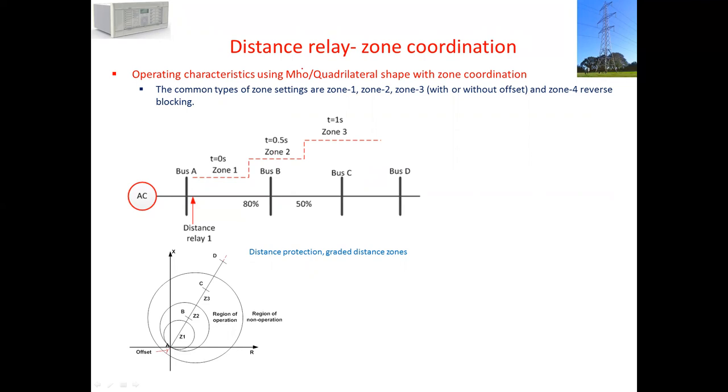If we look at the Mho shapes, the line between A to B is this one. We cover 80%, so around 20% is a gap. Everything within this circle, the relay must operate in zone 1 time, instantaneously. Zone 2 is at 50% of the next line between B to C. Anything within this area, the relay should provide trip time at 0.5 second. Zone 3 is after 50% of line C to D, somewhere around here.